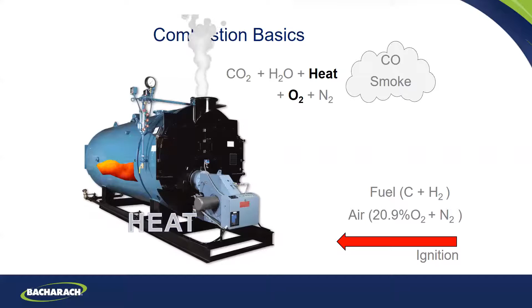I'm going to just graph these gases briefly here, just to give you an idea of how they relate to each other. So this is called the stoichiometric chart. It's really a chart that will let me graph the gases. So on the left-hand side here, these are percent by volume gases. So this chart would go from 0, 2, 4, 6, 8, 10, and probably around to 14. I don't have those numbers on here because this chart is different for every different fuel. So you'd have a different one for number 2 fuel oil, number 4 fuel oil, or 6, you'd have a different one for propane, natural gas, what have you. So we don't put numbers on the side.